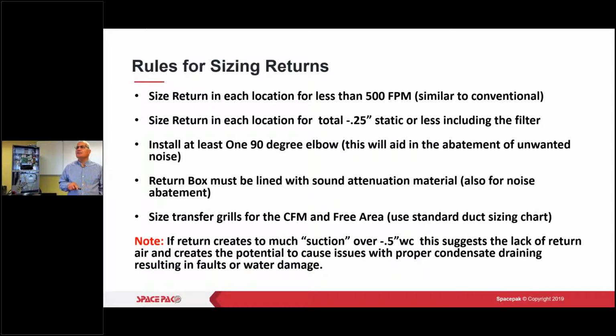Size return in each location for a total of 0.25 static and less, including the filter. Install at least 1 90-degree elbow. This is important because this is going to drop the noise. So don't just have that return that we give you wrapped up in one straight horizontal configuration. We do want to have a 90-degree bend in there. The return box has to be lined with sound attenuating material, also for noise. And obviously we want to keep it clean.